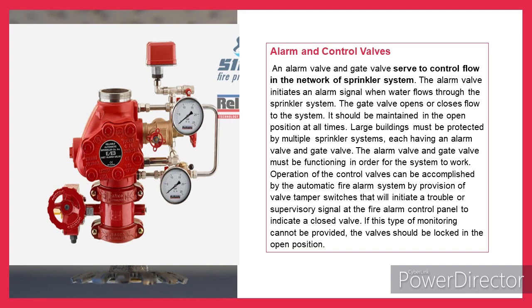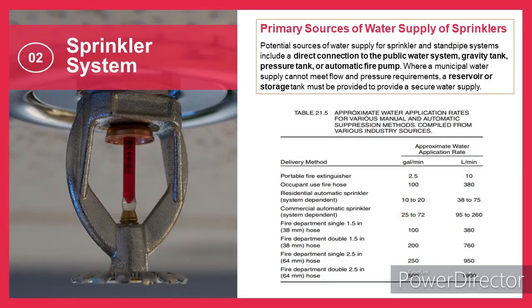If this type of monitoring cannot be provided, the valves should be locked in the open position. Here are the primary sources of water supply of sprinklers. Potential sources of water supply for sprinkler and standpipe systems include a direct connection to the public water system, gravity tank, pressure tank, or automatic fire pump. Where a municipal water supply cannot meet flow and pressure requirements, a reservoir or storage tank must be provided to provide a secure water supply.